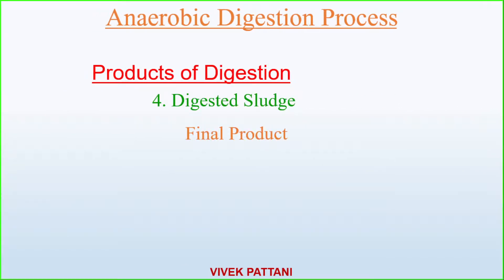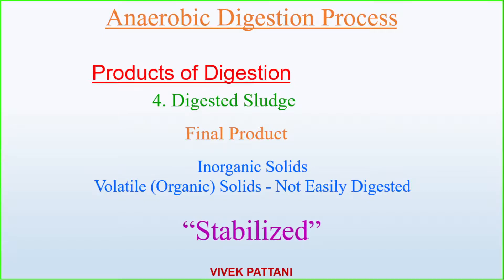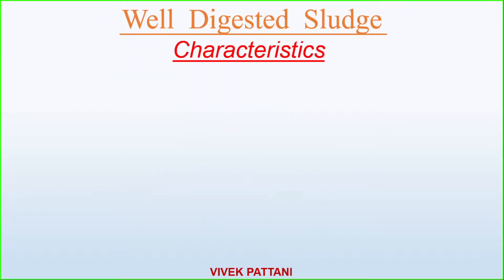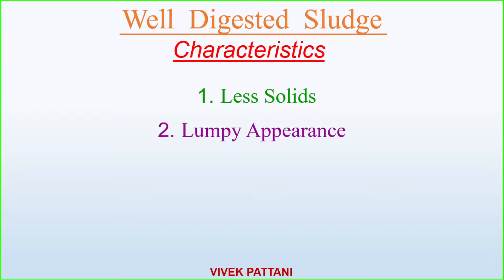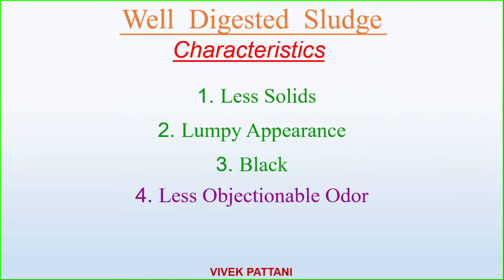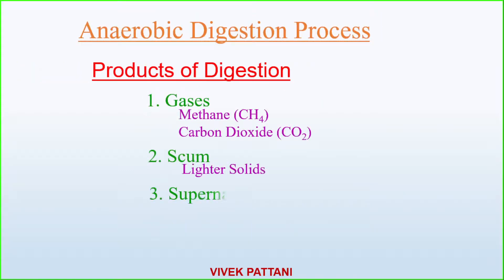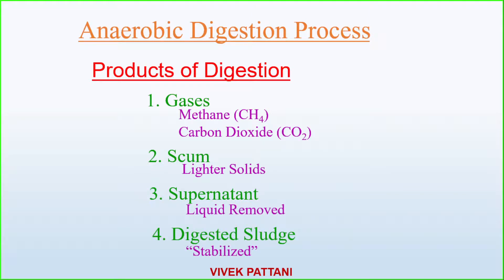The final product is digested sludge, which contains inorganic solids and volatile organic solids that were not easily digested. The sludge is ultimately stabilized. Characteristics of a well-digested sludge include a reduced amount of solids, a lumpy appearance, black color, less objectionable odor, and reduced volatile content.